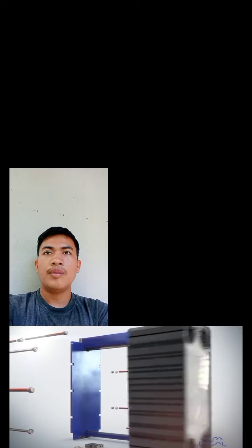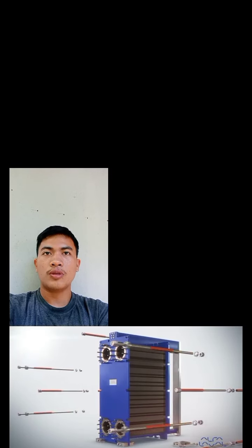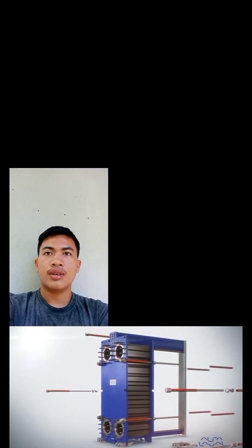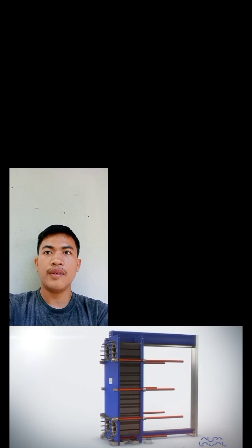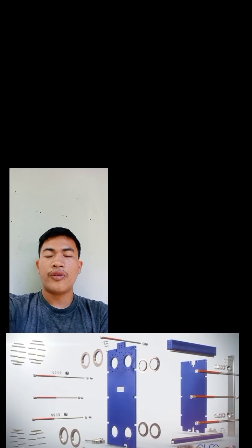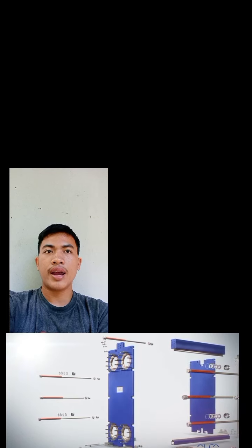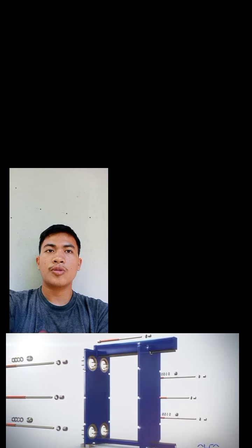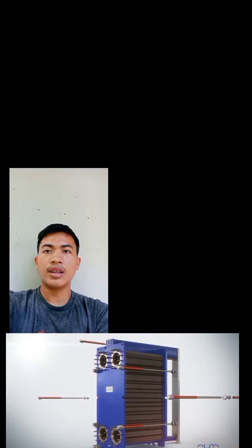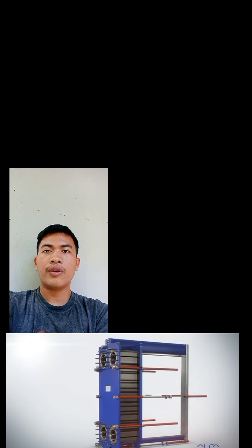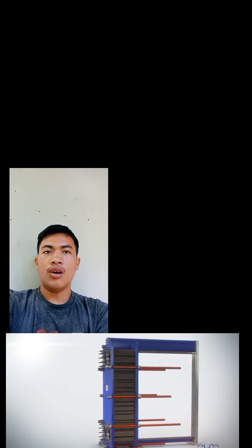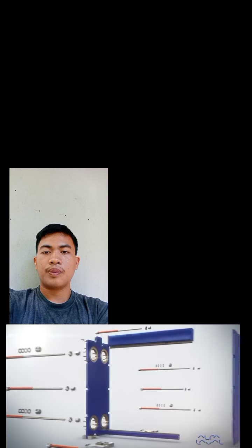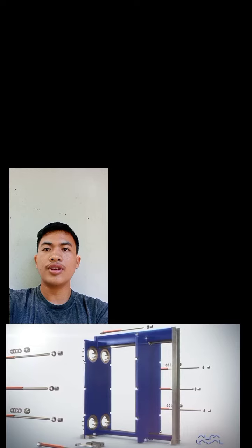Step 2. Remove plates. Safety reminder: always wear gloves when handling plates, as the edges are sharp and can cut your hands even if you are very careful. The movable frame, the back frame, can be slid back to the support column along the guide bar, exposing the plates. Remove the plates one at a time by sliding them back to the removal frame. Remove the hanger and tilt the plate off the guide bar. Always be careful not to bend the plates when removing them, or they would not be able to form a proper seal, and your plate heat exchanger will leak.